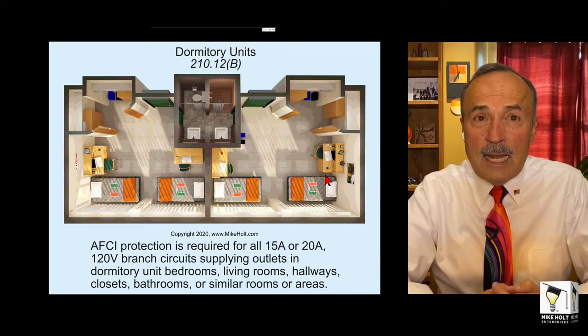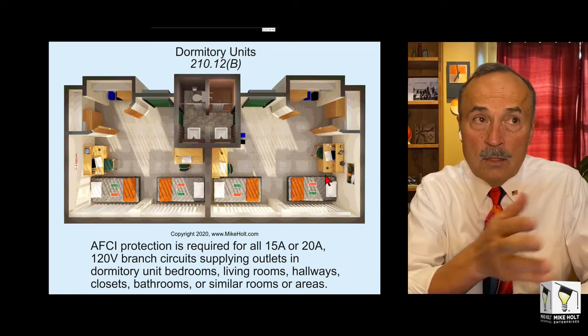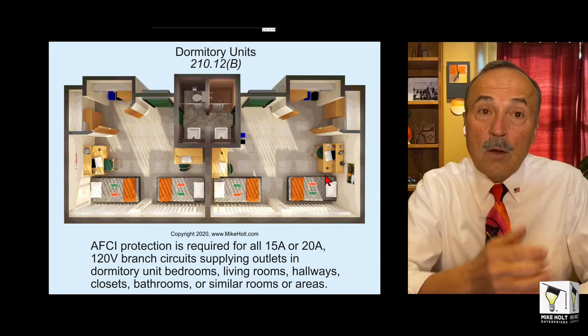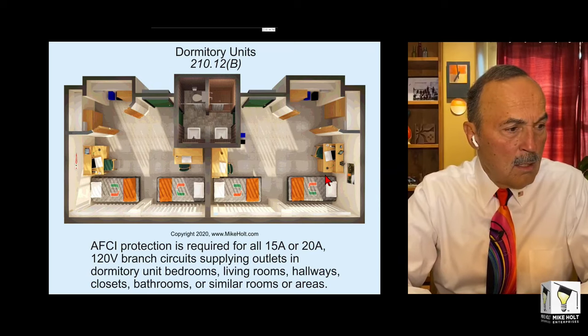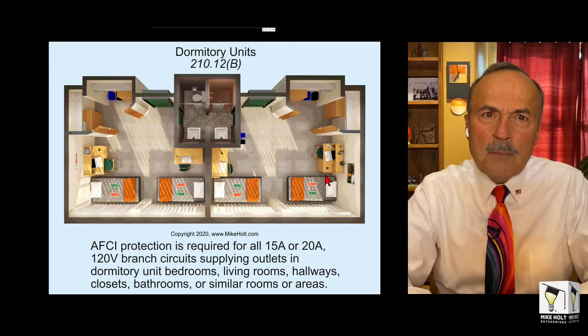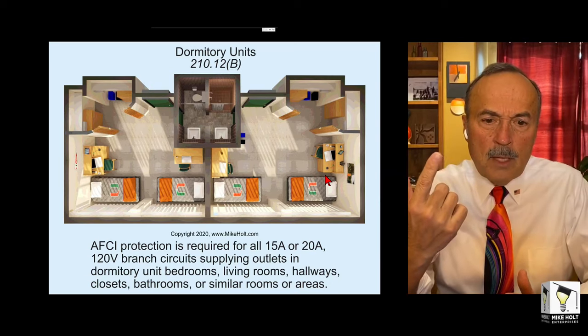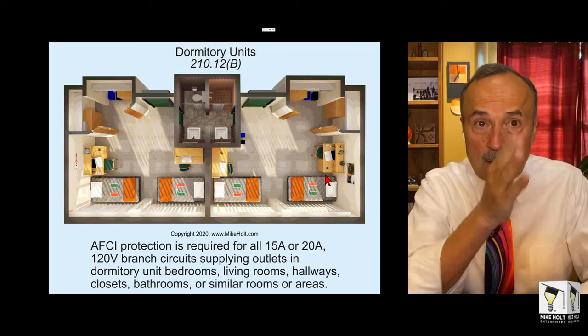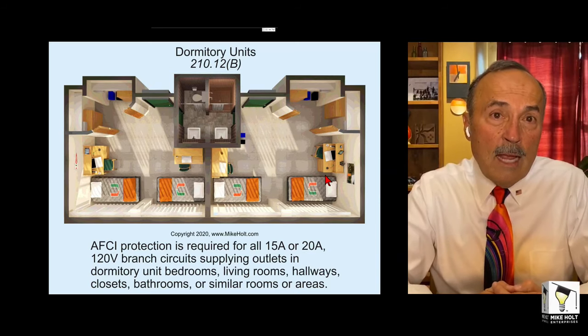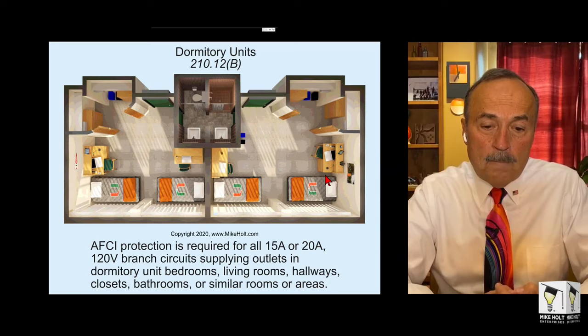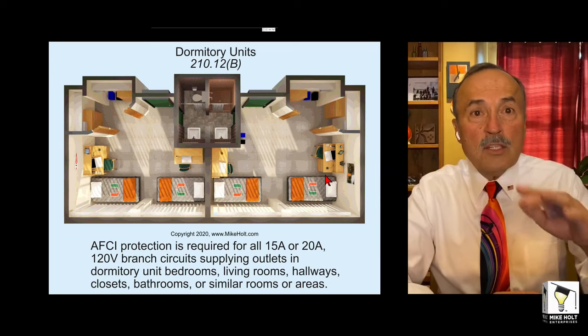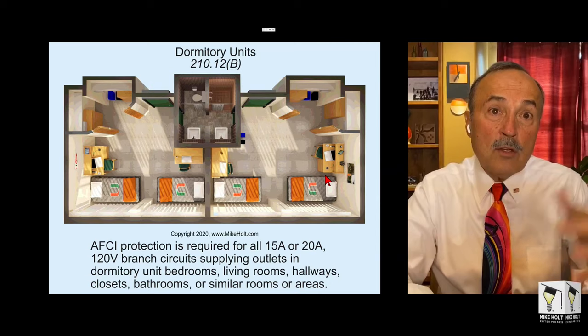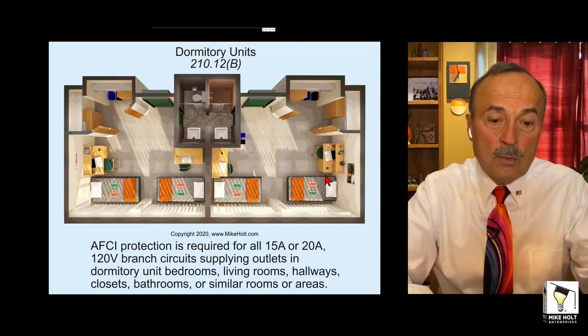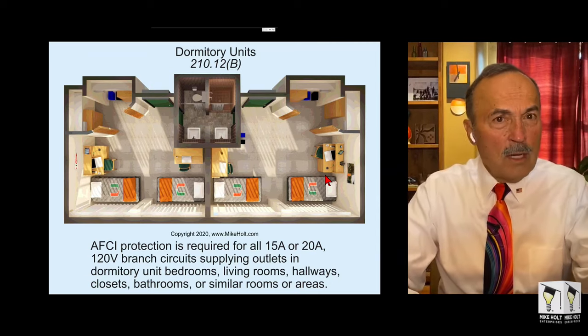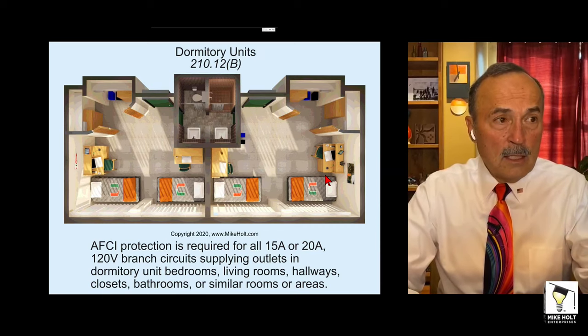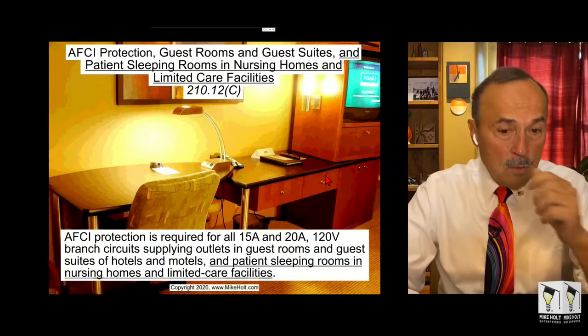This came out in 1999, the very first AFCI requirement. So we're talking 1999 to 2020. Holy crap, that's more than 20 years. Is that possible? Yes, check my math here. I can't believe that. Okay, so in 1999 they required AFCI protection for dormitories. And by the way, in the 2020 code they added a definition of what a dormitory is, they defined the term dormitory. So it's not only residential, all the places in a residence, and then it's going to be in the dormitories.